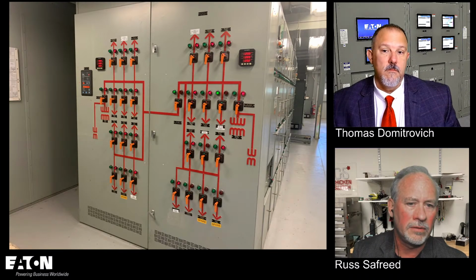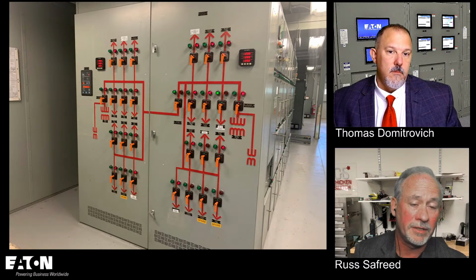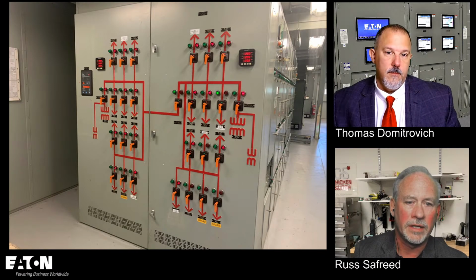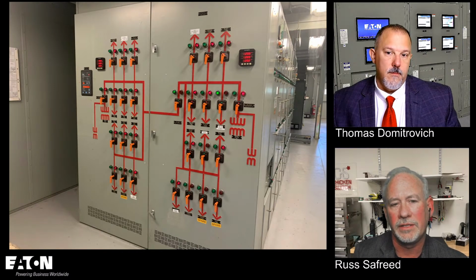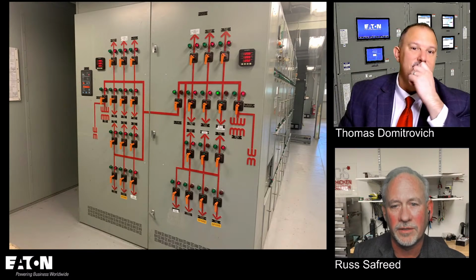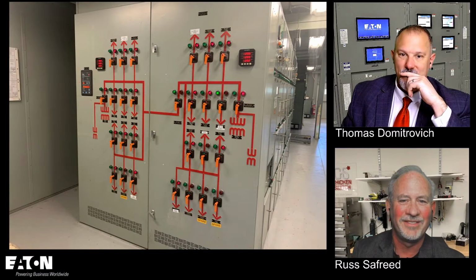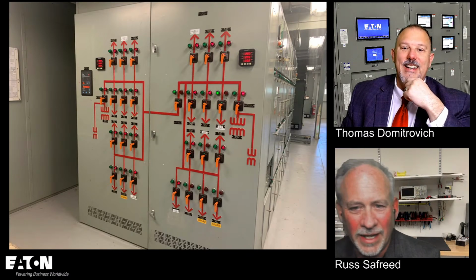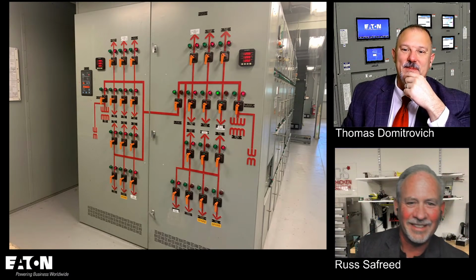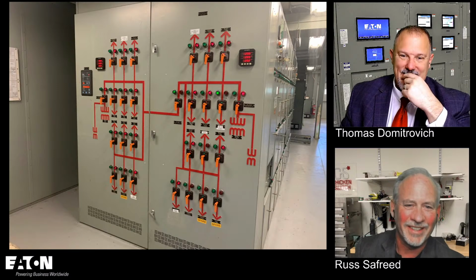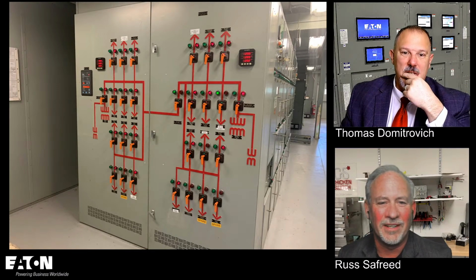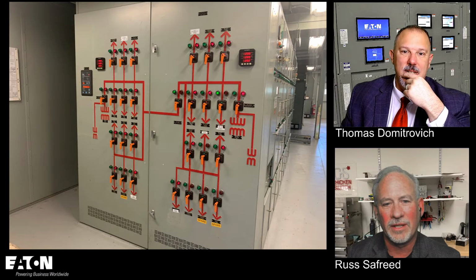Downsides, the pros and cons here. The pro is it works well because the guy doesn't have a choice. The con is these installations, you got to be careful because it's pretty easy to get your hand on the wrong handle when it comes time to open a breaker. So you're always worried about it when you're getting ready to go into a shutdown and doing switching. Did he grab the wrong handle? So you might want to think, if you have one of these, about how you control that.